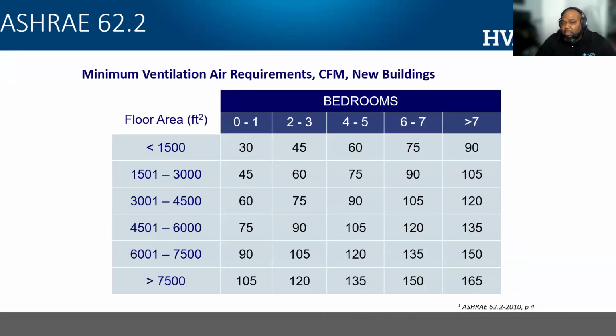And really, it goes something like this. We're looking at a house that has about 1,500 square feet of floor area, and maybe a house that has 2 to 3 bedrooms. We would want to select and purchase a fan that can deliver that amount of CFM, 45 CFM, to properly ventilate that house. All right, so that's ASHRAE 62. Wherever you are located in the country, you probably have an adoption of some year of 62.2, and to use the most appropriate formula, you want to verify with your organization or agencies which year you've adopted, because things do change from year to year.